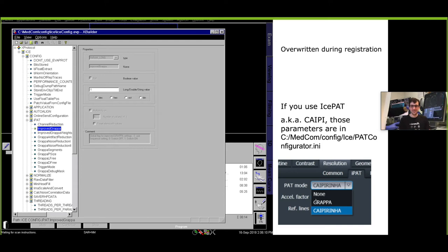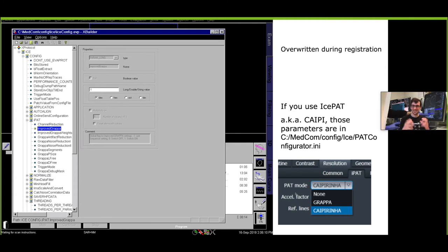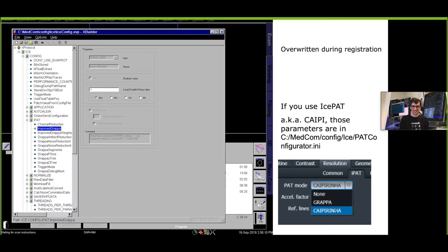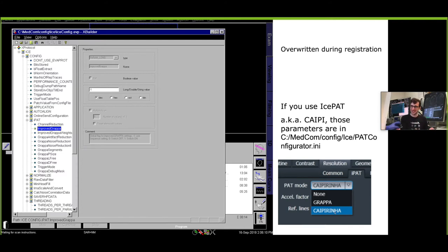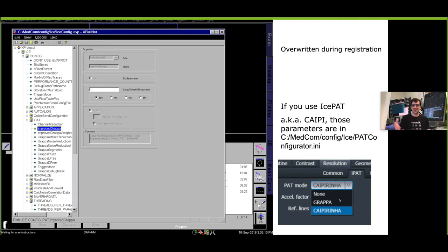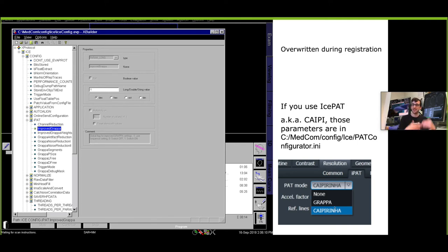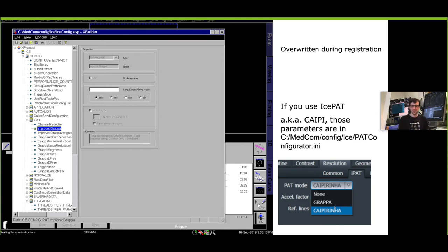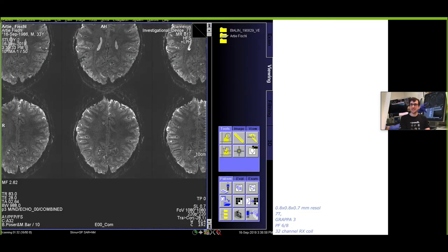Maybe I should say a few words about the terminology here. PAT means parallel acquisition and undersampling your images and then trying to recover the missing k-space lines based on a reference dataset. You can select GRAPPA and CAIPIRINHA on most of the sequences in the Siemens environment. GRAPPA just refers to a simple 2D reconstruction. CAIPIRINHA does not mean in this case that you need to do a CAIPIRINHA field of view shifting. It's just a different algorithm, a different reconstruction pipeline. You can do CAIPIRINHA with the same in-plane acceleration as you do with GRAPPA. However, then you're not using iPAT but you're using something that's called Ice PAT. In CAIPIRINHA you have additional functionalities, for example there you can also do the CAIPIRINHA field of view shifting or even do it in a 3D fashion.